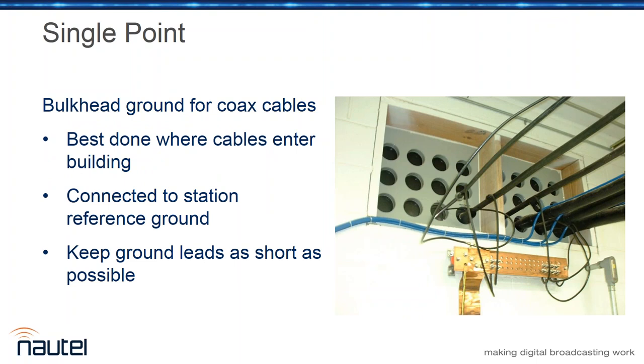Wherever coax cables enter a building, we like to see the shields grounded. Now again, working with the theory that there is nothing perfect, no perfect site, this one has an issue as well. You'll notice that the grounds are looped, so they're longer than they need to be. That adds additional inductance, which adds additional resistance or impedance to lightning energy. And with the loop, well, they add some more inductance with the actual shape of them. So we want to keep our grounds as short and straight as possible.